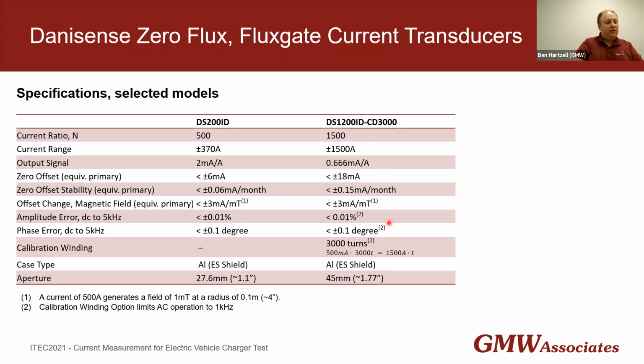The second one I'm going to mention here is a DS1200ID-CD3000. It's a higher current range transducer. You can see 1500 amps peak. But it has the addition of a calibration winding of 3000 turns. So this is an additional winding around the core of the transducer, allowing an in situ calibration check of the transducer. If the calibration winding is injected with 500 milliamps multiplied by the 3000 turns of the calibration winding, we end up with 1500 ampere turns. That's the same as the full scale of this transducer. So by just doing a very low signal, we can simulate a full scale primary current.